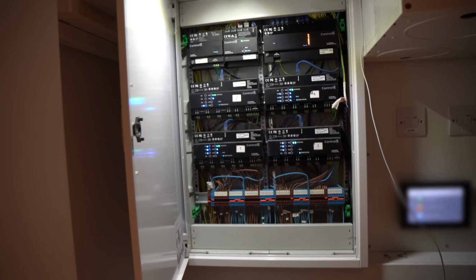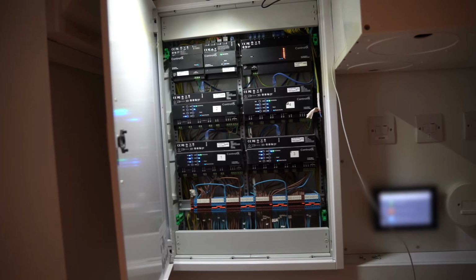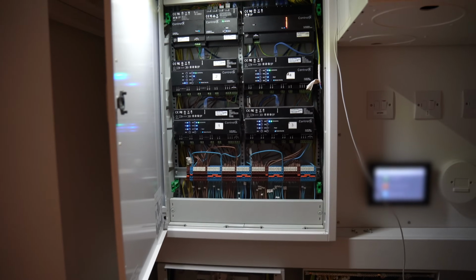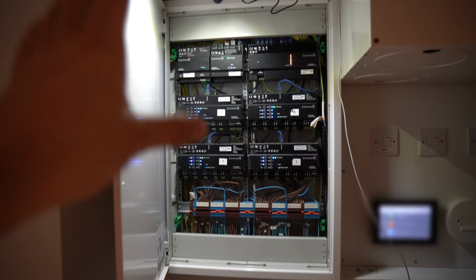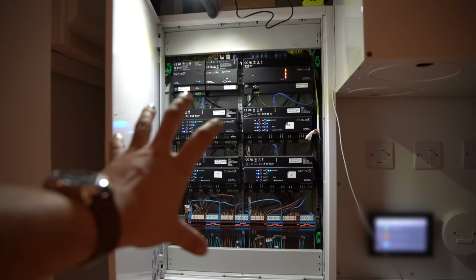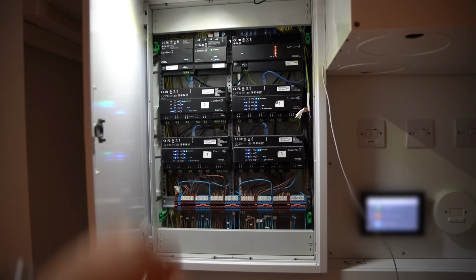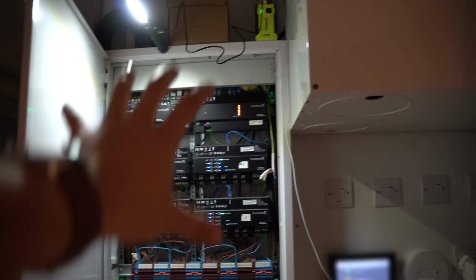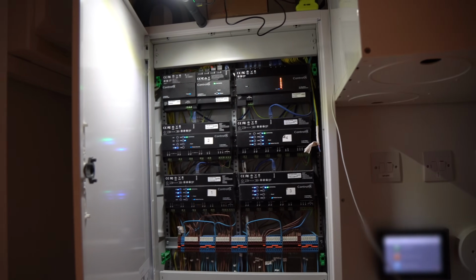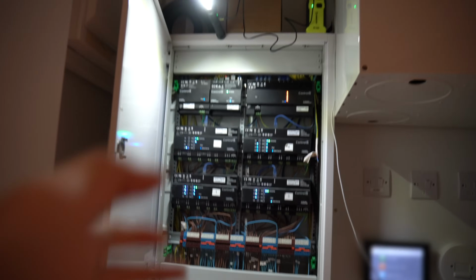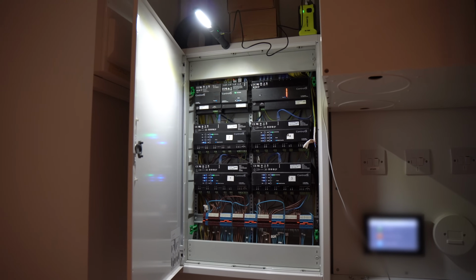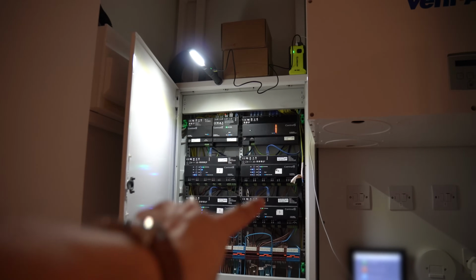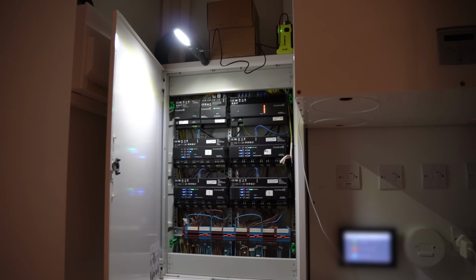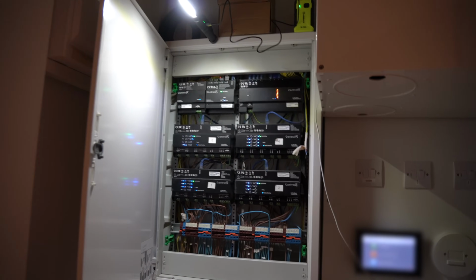What it can do is pull, if you've got IP-ready home products, whether it be air handling or blinds, lights, anything you can think of, access control, this will basically pull that and put it into one hub to operate it from. The problem is, all of these are on one breaker, and I think it's only one B curve breaker, this one down here. So that's not really very ideal, and you're going to get nuisance tripping. So we've been asked to split that into two. So I'll show you how that works and how I'm going to do that.